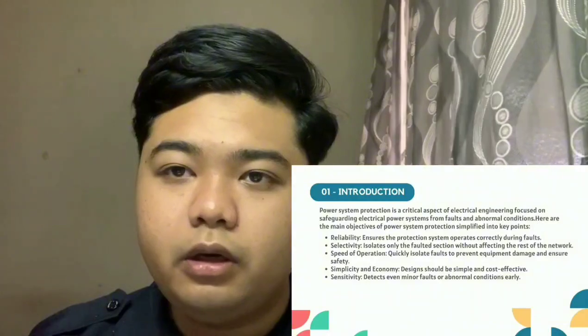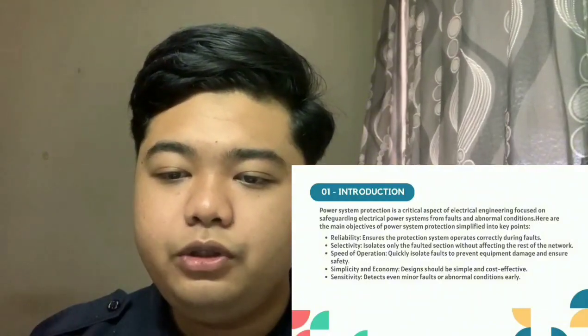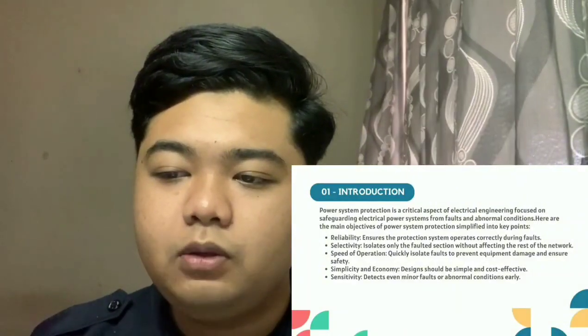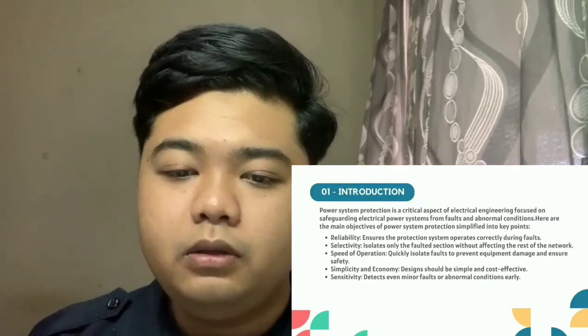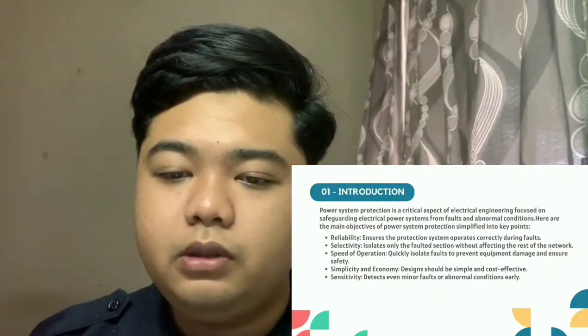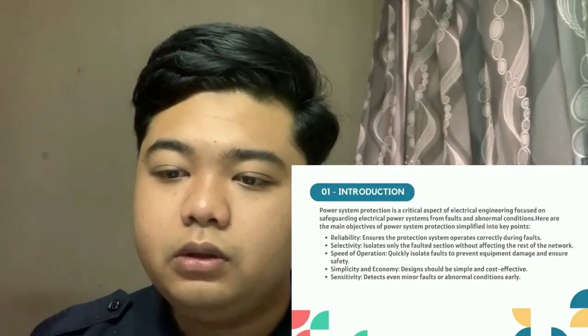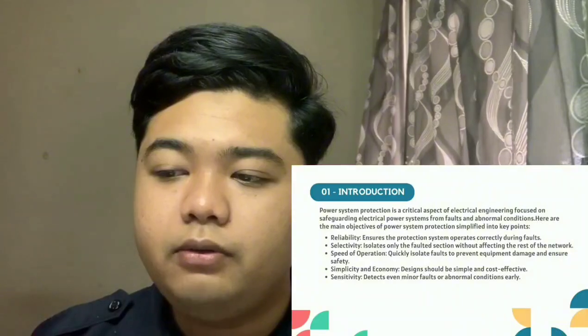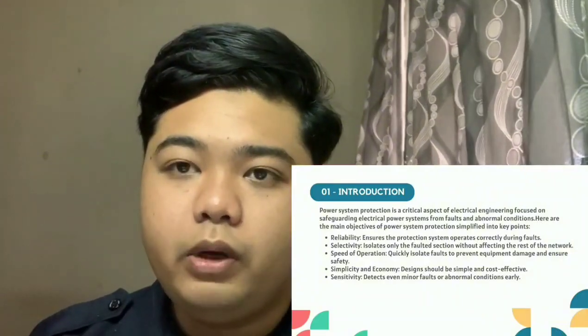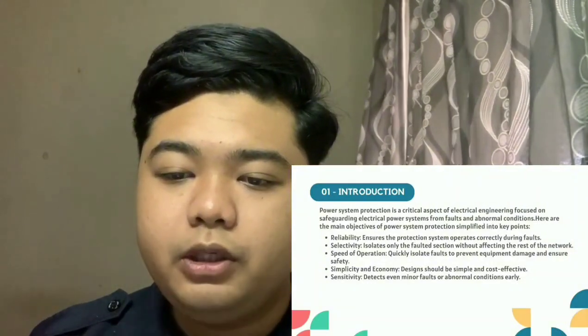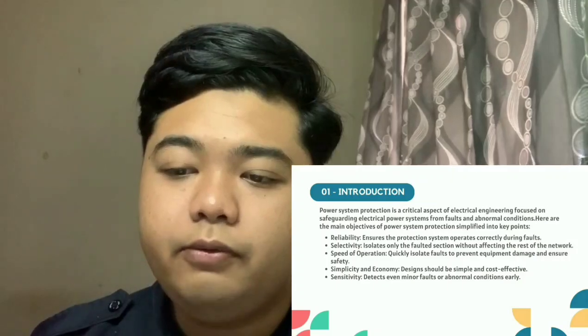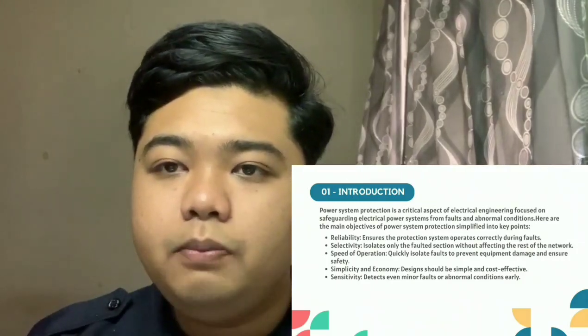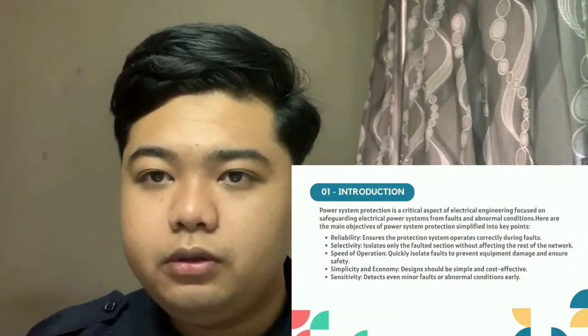The first one is reliability, which ensures the protection system operates correctly during a fault. The second one is selectivity, which isolates only the faulty section without affecting the rest of the network. The third one is speed of operation, which quickly isolates the fault to prevent equipment damage and ensure safety.